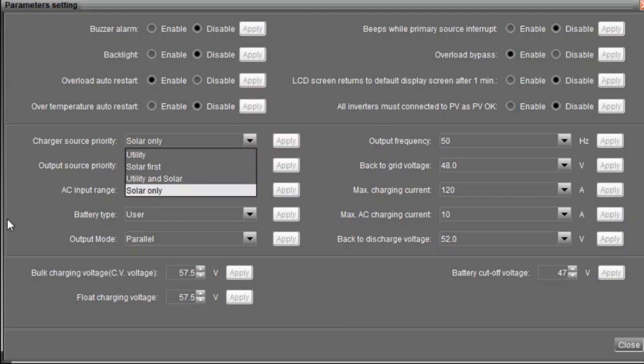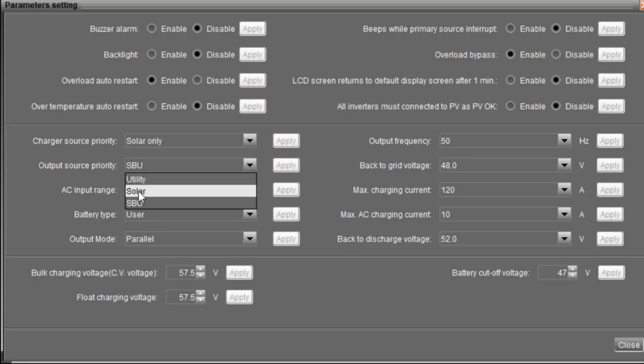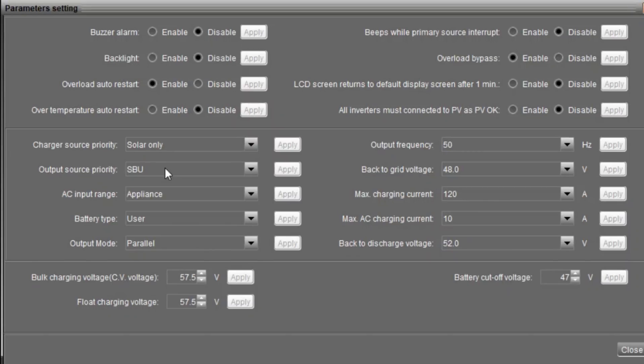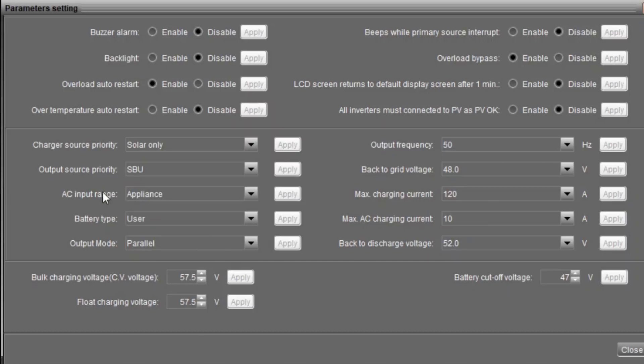Even turned off. Overload bypass is enabled—that just allows it to go to 16,000. Never ever been there. I don't think my shunt trip will actually even take that. Returns to the last screen after a minute, all inverters must be connected to PV as PV OK—I've got that disabled because I don't have PV on both, I've only got PV on one. So charge source priority: solar only. Now that's 98% of the time. Output source priority: SBU, which is solar, battery, and then utility, or you can have it on utility or solar.